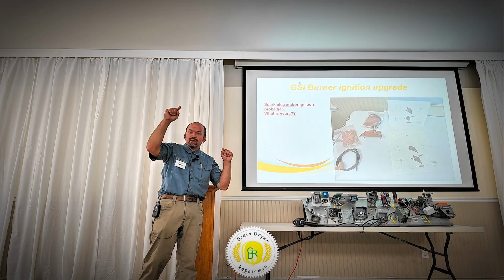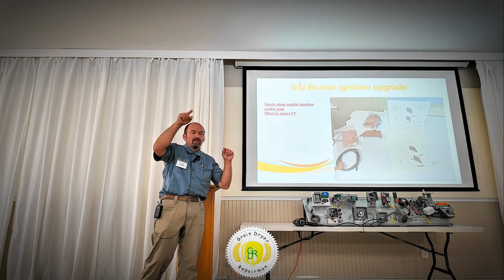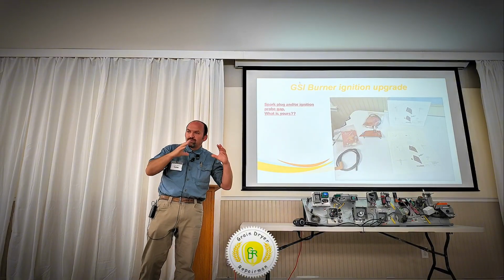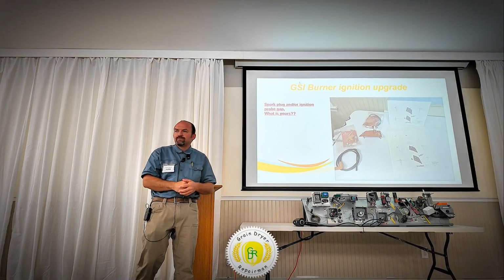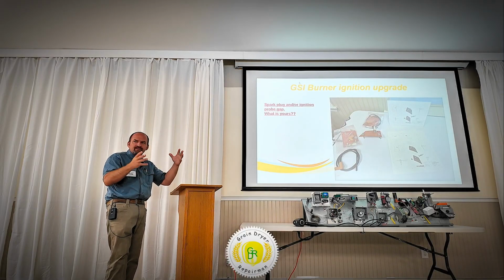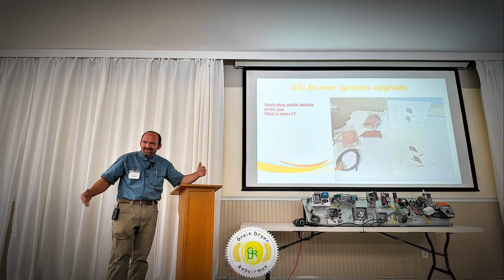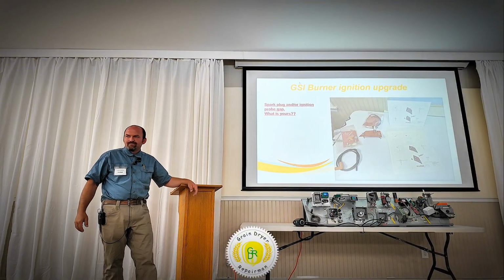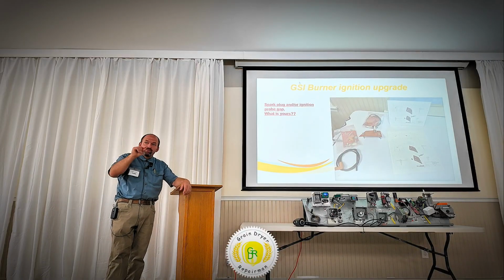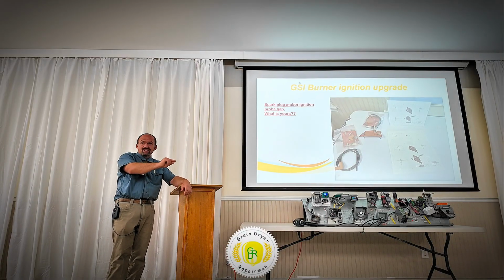So you still need that B ground connected to the one side of your ignition probe, and then also connected to your ground bar, so that your board is actually grounded out. Because the arcing to that B ground, if not connected, works better if it's grounded. All grounds should be bonded together. And the flame sensors can be interconnected together. Yes. Okay. Perfect. But the flame sensor needs to be hooked to the probe. The ground wire going next to the flame sensor needs to be hooked in the same as that B ground.